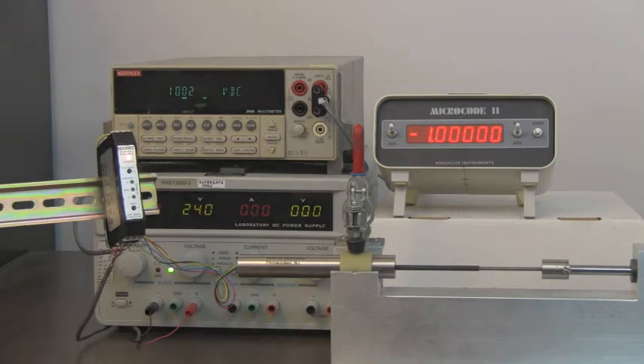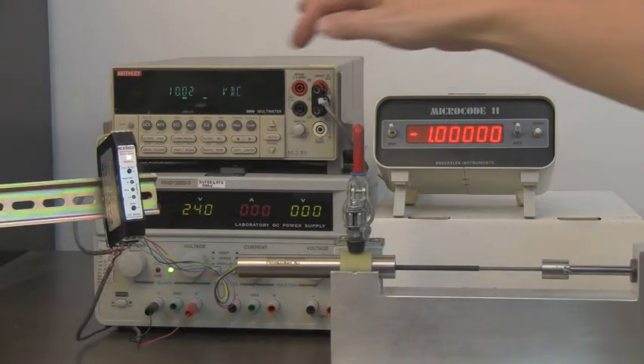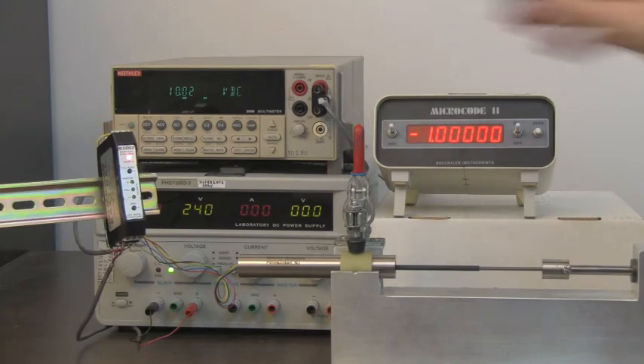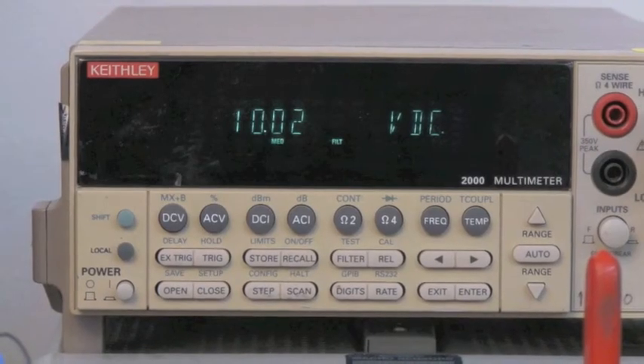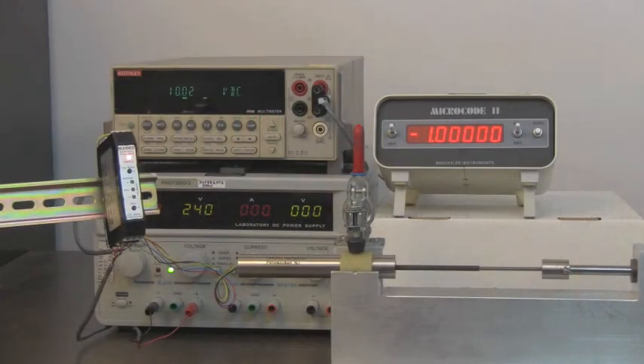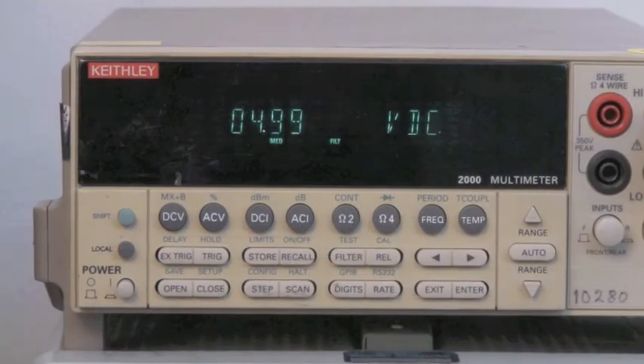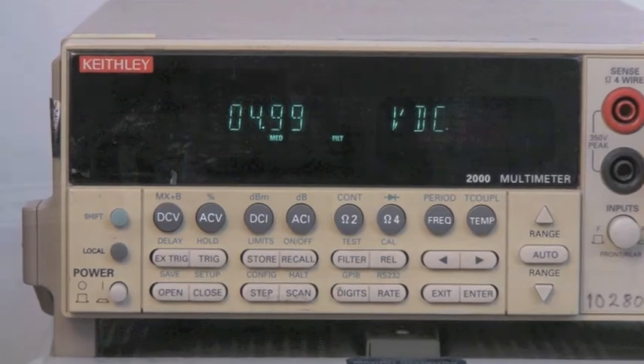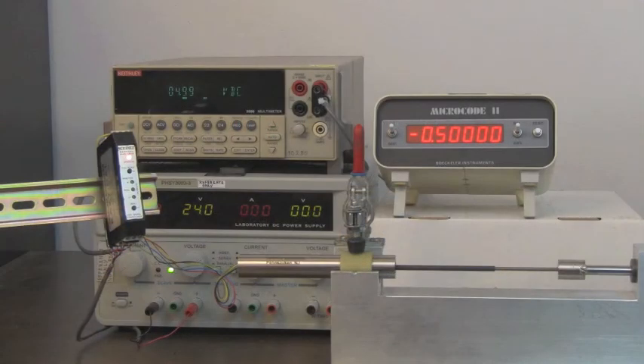Indicating that calibration has been successfully completed and normal operation mode is engaged. We now observe that the output voltage of the EasyCal as displayed on the DVM is plus 10.02 volts DC with plus 10.00 volts DC being nominal for the plus 1.0 inch stroke position. We now displace the LVDT back to the plus 0.5 inch position and we observe the output to be plus 4.99 volts DC with plus 5.00 volts DC being nominal.